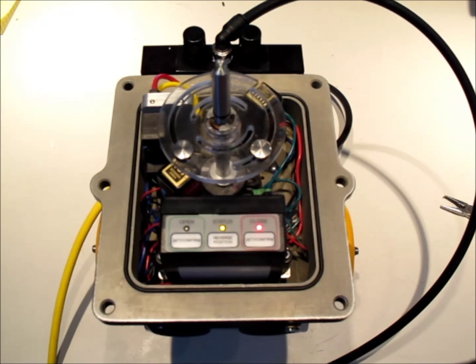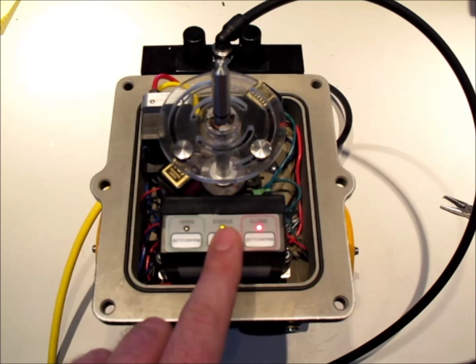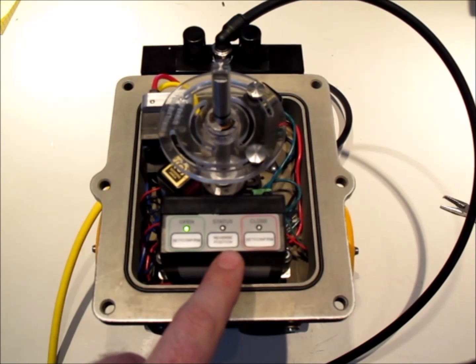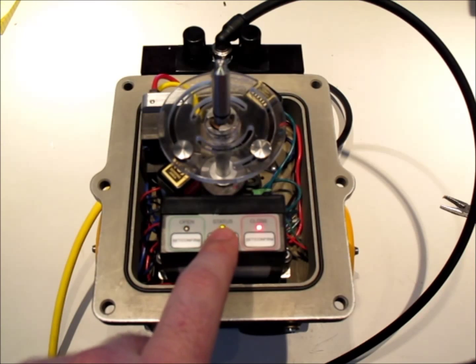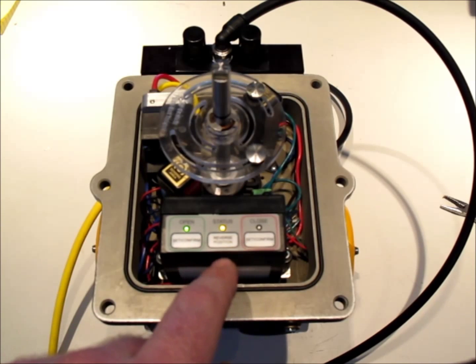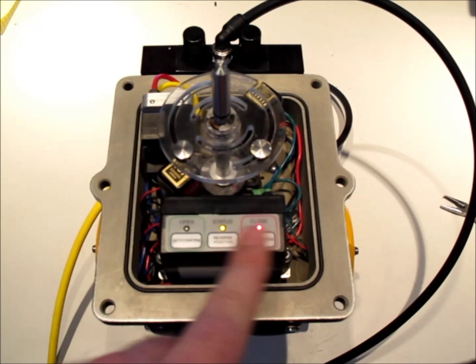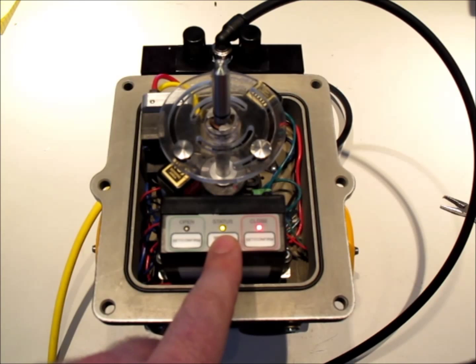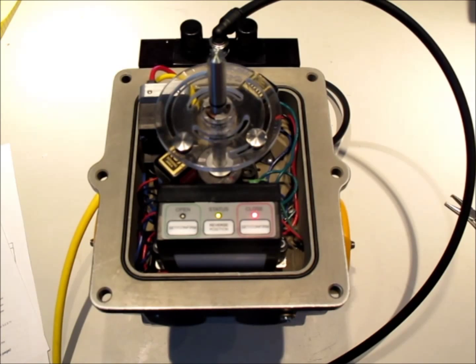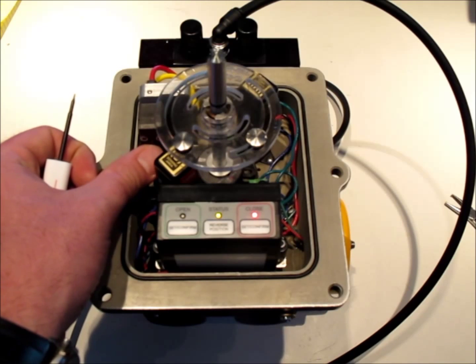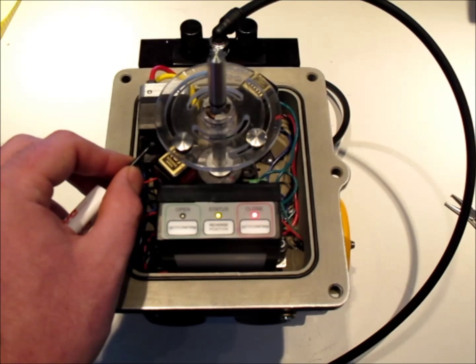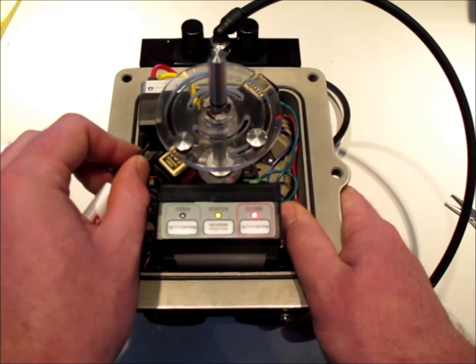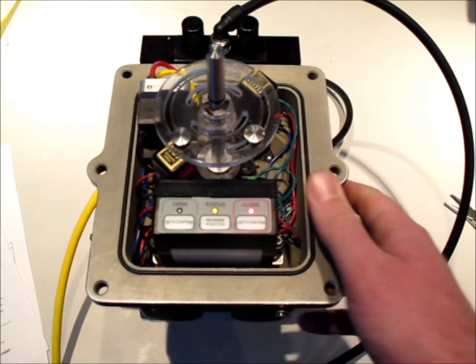Once you've placed the resource and the transducer block out of service, you can reverse the valve with the button board. You'll notice the LEDs for the close and the open illuminate when that switch is made. You can manually override your integral solenoid by finding the small button on the back of the piezo. Using a screwdriver, press and hold this override. Once you release the override, you will return to normal status.